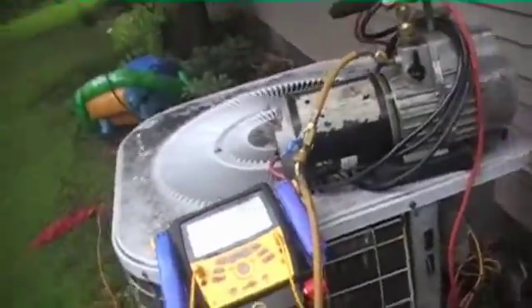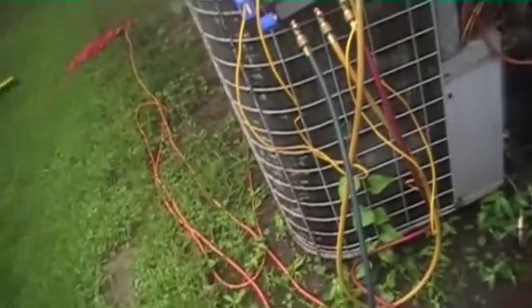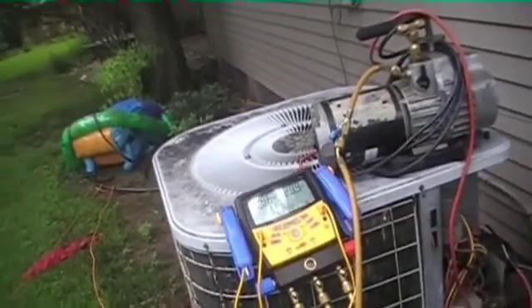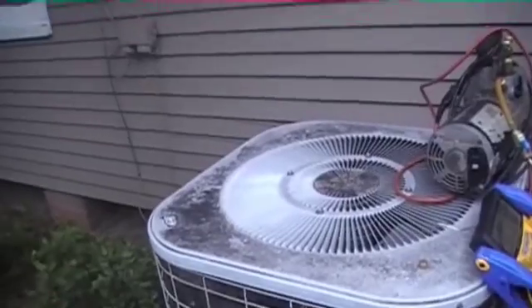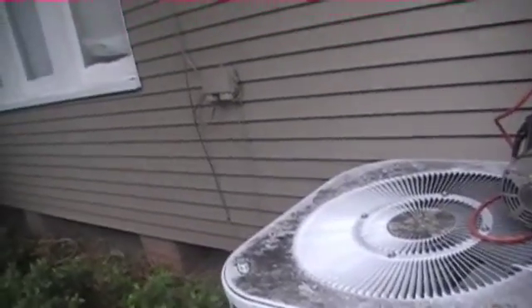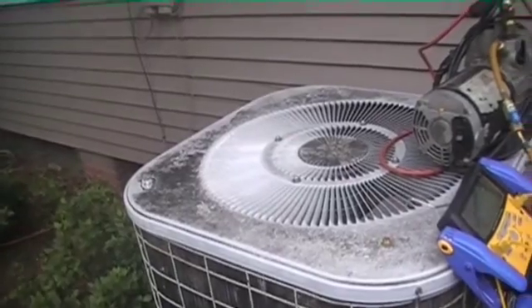I wanted to do a much better video than this but I'm not going to get to because it's been raining here and I've been trying to bust ass and get done before the rain. So it's in a vacuum. What we did here is we replaced the TXV. This is a 1991 Temp Star hooked on a 95 Trane gas furnace and a 95 Trane evap coil — so back in 95 somebody changed out the coil and furnace and left this outdoor unit. I came out here the other day for a no-cool: TXV was bad.